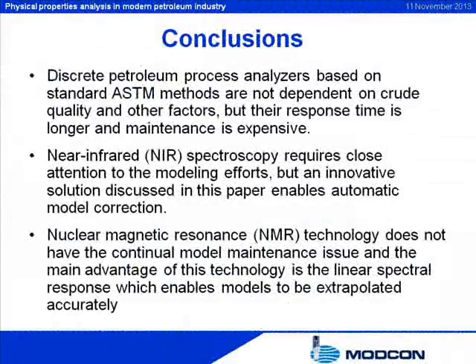In conclusion: discrete petroleum process analyzers based on standard ASTM methods are not dependent on crude quality and other factors, but their response time is longer and maintenance is expensive. Near-infrared (NIR) spectroscopy requires close attention to modeling efforts, but an innovative solution discussed here enables automatic model correction. Nuclear magnetic resonance (NMR) technology does not have the continual model maintenance issue, and the main advantage is the linear spectral response which enables models to be extrapolated accurately. Application of all three technologies is discussed to reach optimized performance, accuracy, and availability in petroleum process analysis.